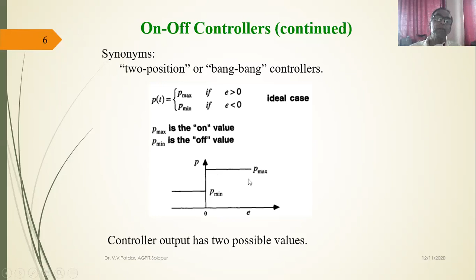That will be the practical case of an on-off controller, which is called the dead band. Earlier it was switching on and off only at zero error value. But what I discussed just now, instead of switching at zero error value, if it is set for 10 degrees Celsius, I'll be switching it on at 10 plus 2, 12. So delta is plus 2 and minus delta is minus 2. It will be put on at 12 degrees Celsius instead of 10. So it will be full on.